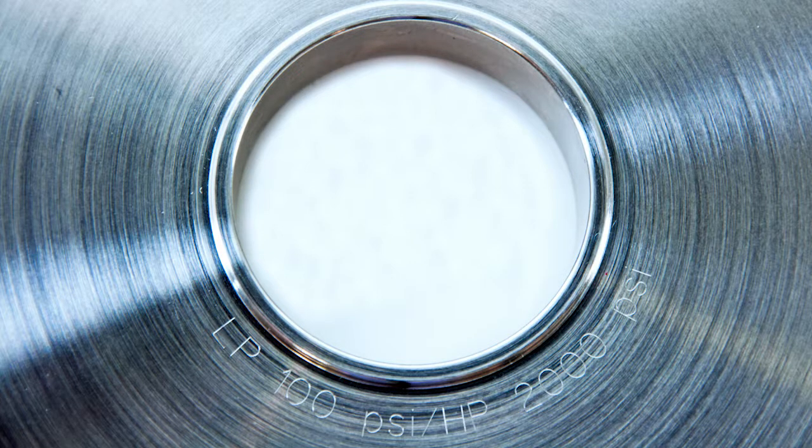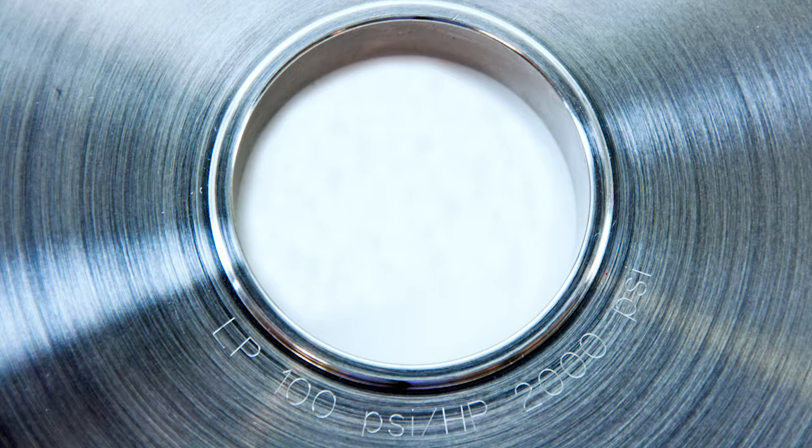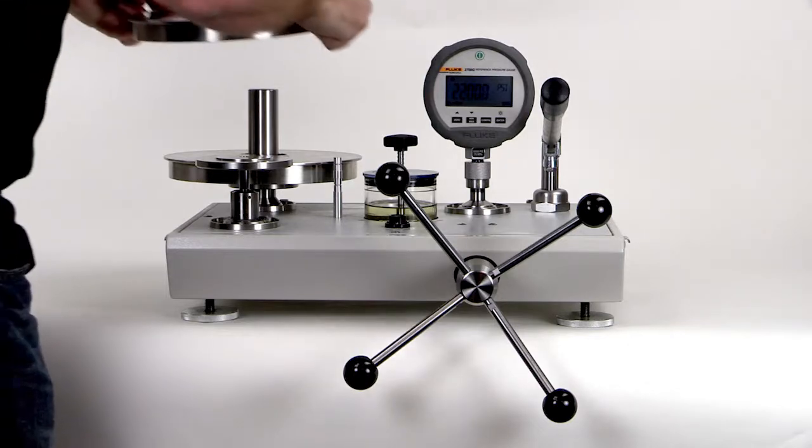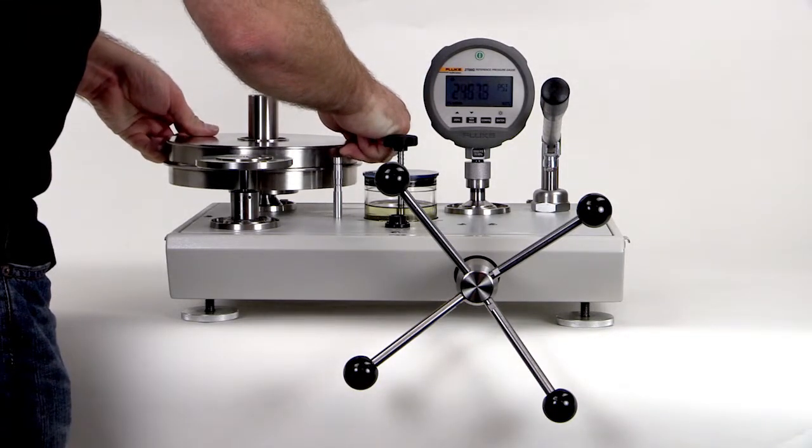The second approach is to perform no calculations at all at the time of use. In this scenario, the masses for the deadweight tester are often marked with their corresponding pressure when used with a particular piston cylinder. You simply add up the values on the masses to determine the pressure being generated.